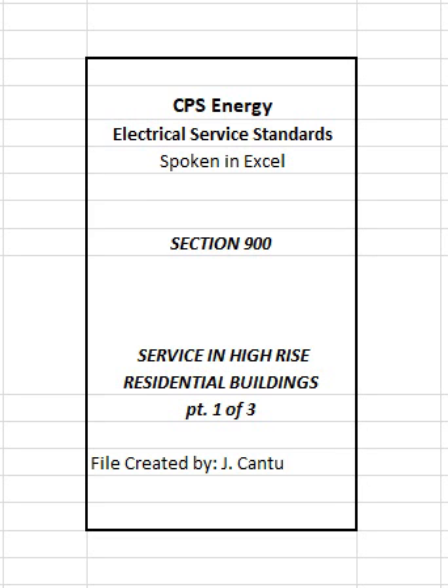B. Feeder raceways. The raceways used for the feeder conductors inside building shall be rigid metal conduit, RMC, or intermediate metal conduit, IMC. Where busway is used, it shall be non-ventilated and accessible for maintenance by CPS Energy. Raceways shall be continuous from the source of supply taken at customer's service equipment on the ground floor to customer's disconnecting device ahead of metering in pre-approved meter room on every third floor. All couplings shall be threaded.